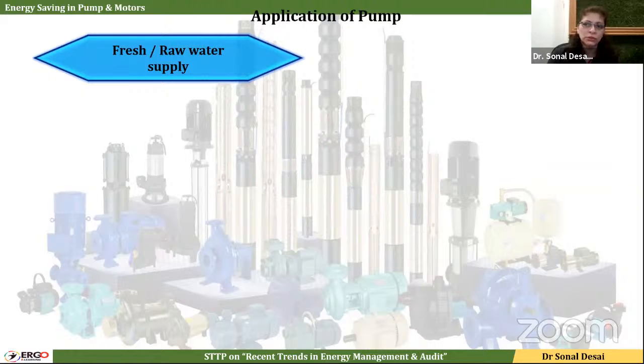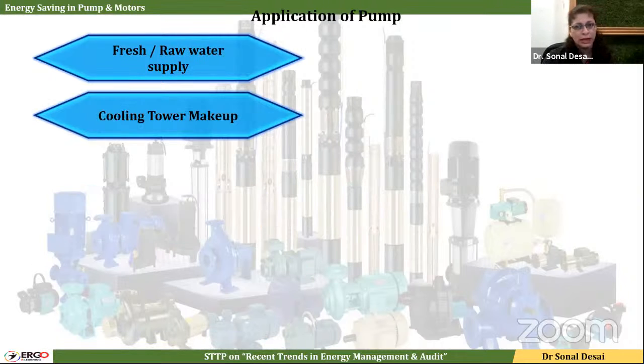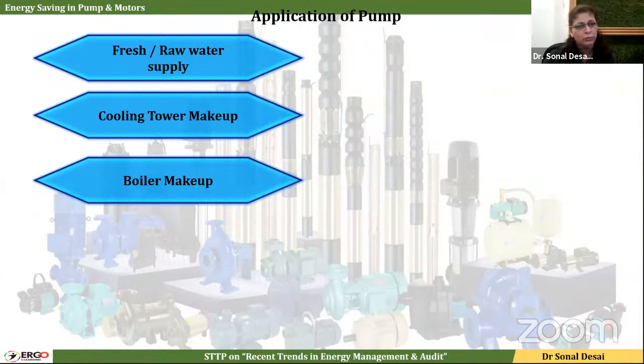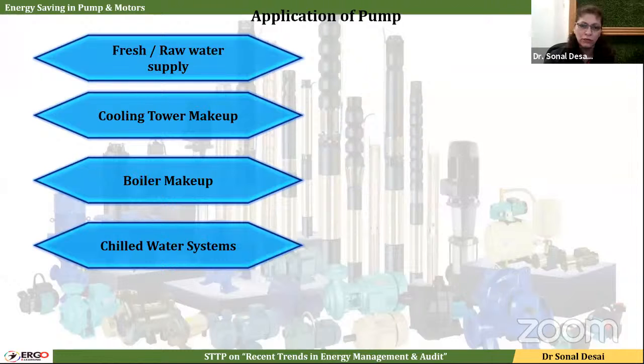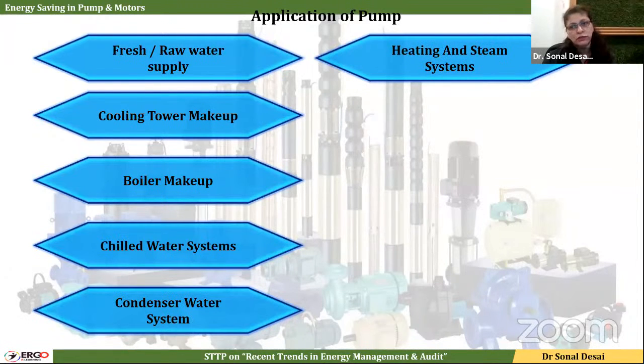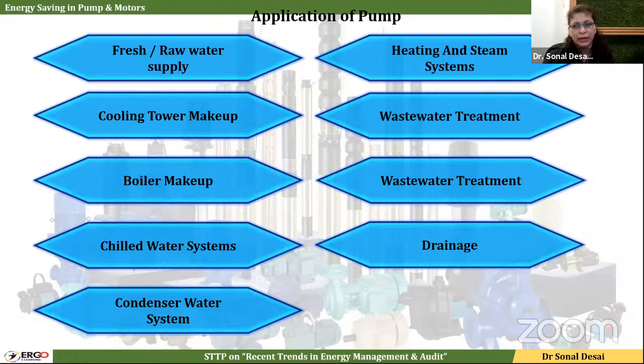In short, if you look at where a pump is used, knowingly or unknowingly, it is used in almost all industrial applications and some domestic applications also. It is always used for pumping of water. Whenever there is HVAC or a power plant, it is used for cooling tower water supply. It is used in boiler and chemical processes to supply makeup water. Wherever there is an HVAC system, there is a chilled water pump, and cool water produced by the evaporator is again pumped. It is used in a condenser also to pump hot and cold water. In heating systems, whether based on hot water circulation or steam, it is used again. And wastewater treatment also requires pumps. So almost all engineering applications as well as major domestic applications call for one or another type of pump.